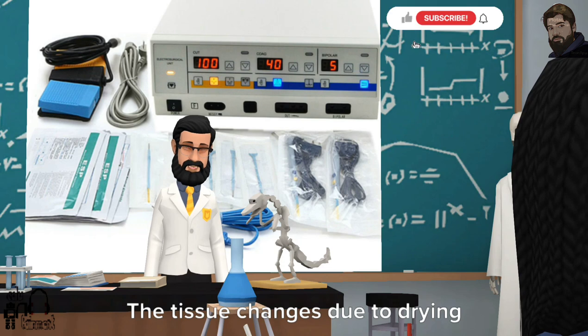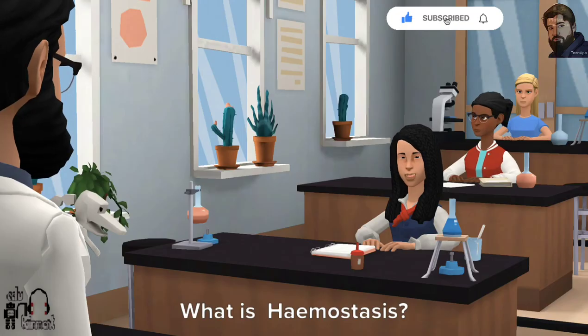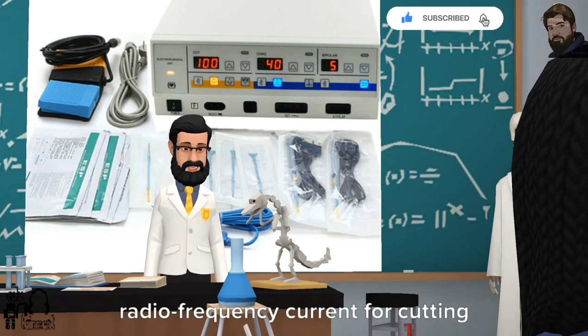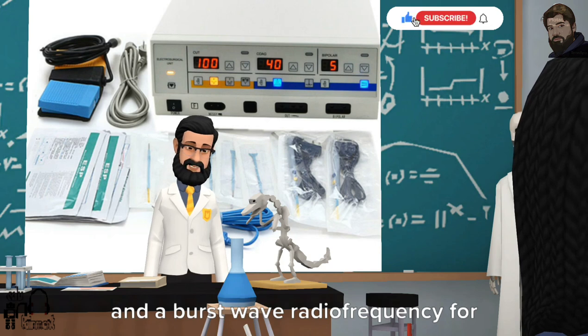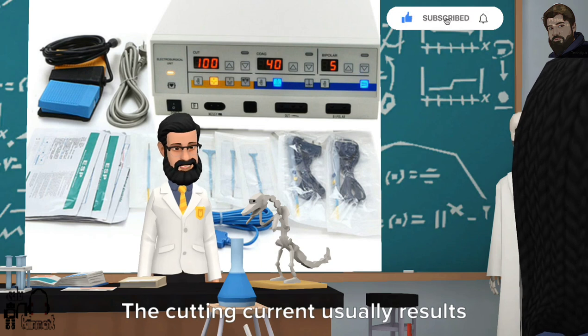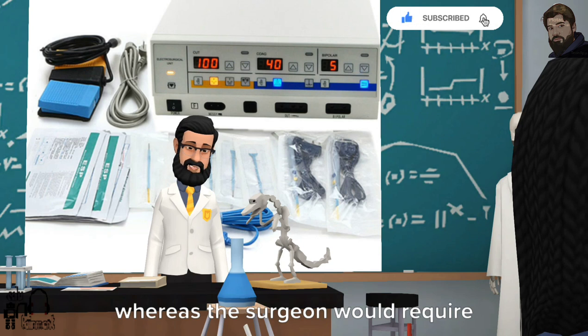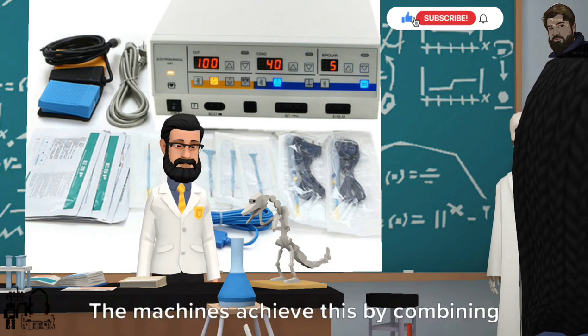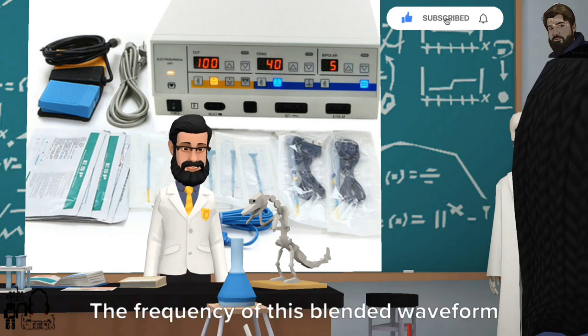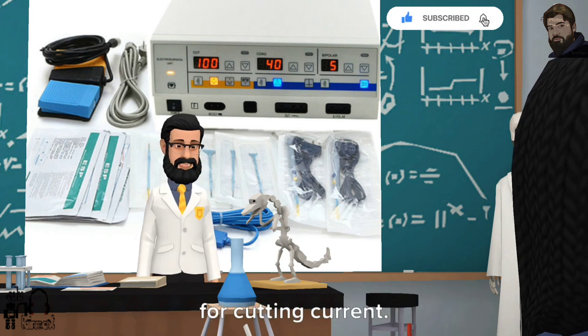What is hemostasis? The concurrent use of continuous radiofrequency current for cutting and a burst wave radiofrequency for coagulation is called hemostasis mode. The cutting current usually results in bleeding at the site of incision, whereas the surgeon would require bloodless cutting. The machines achieve this by combining the two waveforms. The frequency of this blended waveform is generally the same as that used for cutting current.